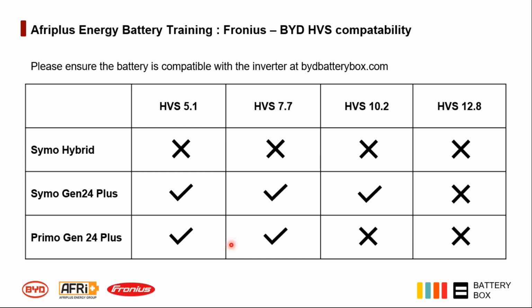I do believe this question has been asked a couple of times, so I'd just like to address it here. The reason the HVM isn't being brought in is because the HVM battery is very similar to the HVS. It's typically designed for your larger storage applications, and its maximum current is 50 amps, and the maximum current on your HVS is 25. And your maximum current on your inverter is 22. With regards to your backup, if you wanted 10 kilowatts of backup, you'd actually need 20 kilowatt hours of HVM battery to supply that load.